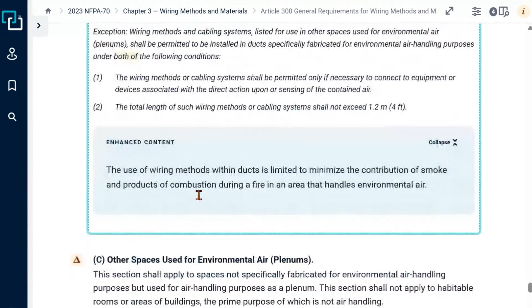So if you see down here, again, you can be in that duct for maybe a fire sensing device or something like that. Okay, then you can be in there. But you're very limited in the type of wiring methods you can put in there. Certainly can't put non-metallic sheathed cable in there. So that's, again, just kind of deviated from the residential, but I just wanted to make it clear.